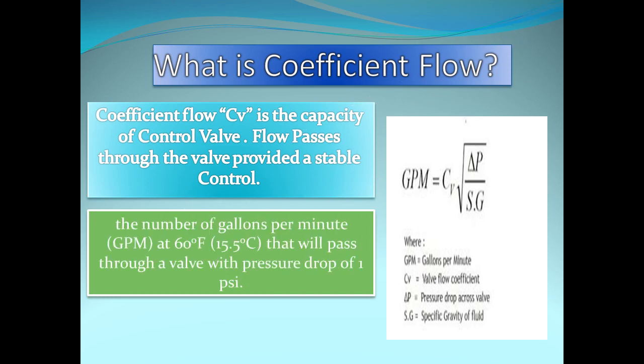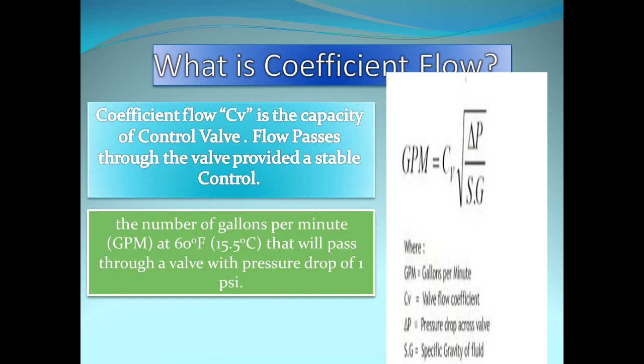What is Coefficient Flow? Coefficient flow or CV is the capacity of control valve. Flow passes through the valve provided a stable control. The number of US gallons per minute at 60 degrees Fahrenheit that will pass through a valve with pressure drop of 1 psi. Here we have a formula. Gallons per minute equals CV, coefficient of valve, under delta P divided by specific gravity.